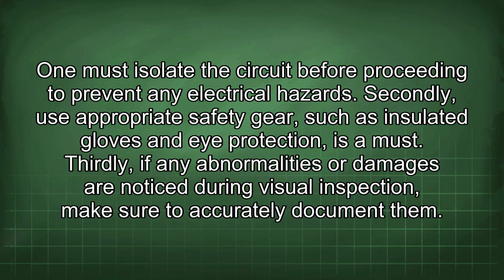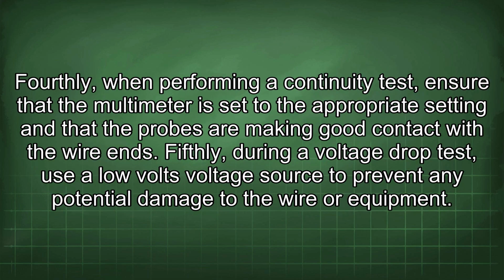One must isolate the circuit before proceeding to prevent any electrical hazards. Secondly, using appropriate safety gear such as insulated gloves and eye protection is a must. Thirdly, if any abnormalities or damages are noticed during visual inspection, make sure to accurately document them. Fourthly, when performing a continuity test, ensure that the multimeter is set to the appropriate setting and that the probes are making good contact with the wire ends. Fifthly, during a voltage drop test, use a low voltage source to prevent any potential damage to the wire or equipment.